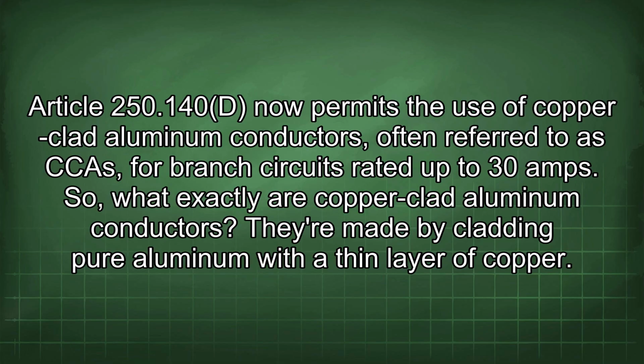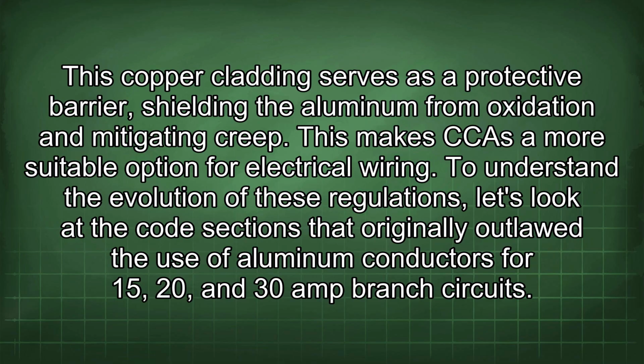More recently, specifically in the 2020 NEC, these restrictions have been relaxed for certain types of aluminum conductors. Article 250.140d now permits the use of copper-clad aluminum conductors, often referred to as CCA, for branch circuits rated up to 30 amps. So, what exactly are copper-clad aluminum conductors? They are made by cladding pure aluminum with a thin layer of copper. This copper cladding serves as a protective barrier, shielding the aluminum from oxidation and mitigating creep.